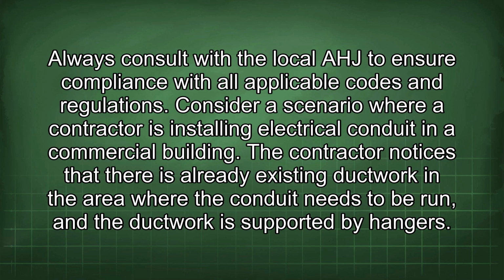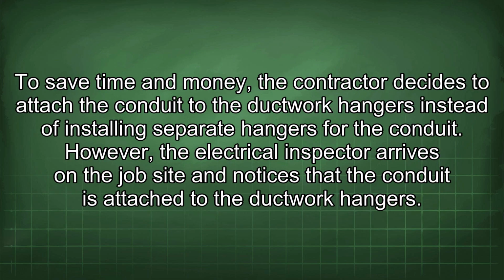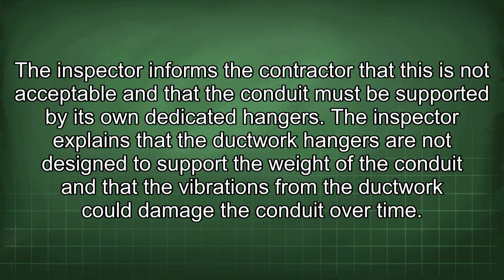Consider a scenario where a contractor is installing electrical conduit in a commercial building. The contractor notices that there is already existing ductwork in the area where the conduit needs to be run, and the ductwork is supported by hangers. To save time and money, the contractor decides to attach the conduit to the ductwork hangers instead of installing separate hangers for the conduit. However, the electrical inspector arrives on the job site and notices that the conduit is attached to the ductwork hangers. The inspector informs the contractor that this is not acceptable and that the conduit must be supported by its own dedicated hangers.